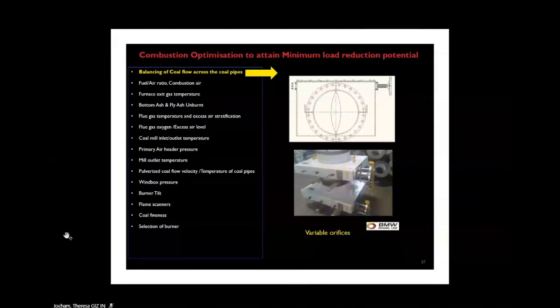Another thing is balancing of your coal pipe. This is very important. And in fact, we are doing it in details in the two stations at DVC and Andal. We are doing it in details. And there is a coal flow measurement being installed by Siemens. And then how do you control the balancing? You measure the coal, but you must have something to measure it. So this is a variable orifice. This is being supplied by BMW. It's an Indian company being manufactured in Calcutta. So this will be a very interesting test run, what we are going to do in Andal.